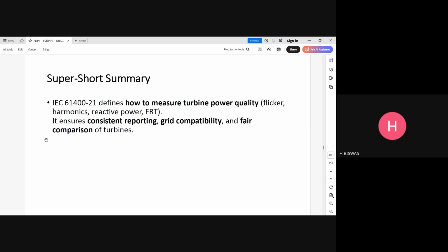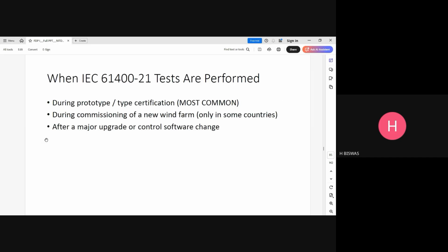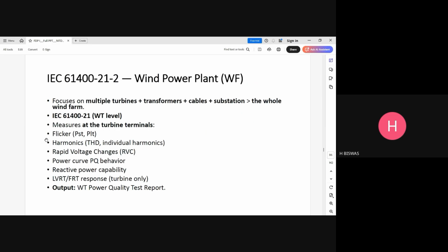So that's the thing. In a super short summary, just to give you a brief idea of how to measure turbine power quality: flicker, harmonics, reactive power, FRT. It ensures consistent reporting, grid compatibility, and fair comparison of the turbines. Now, when are Part 21 tests performed? During prototype or type certification, most commonly, during commissioning of a new wind farm, and in some countries, depending on their grid code requirement, after a major upgrade or control software change.